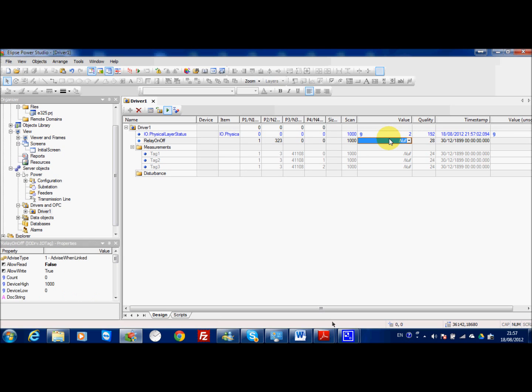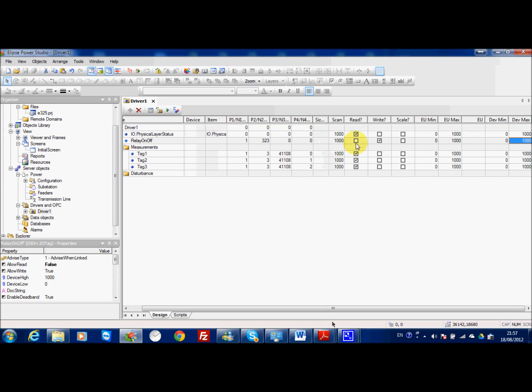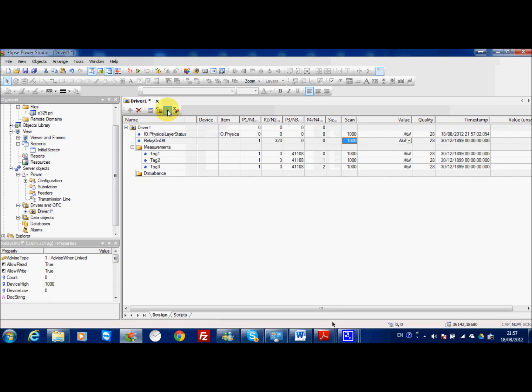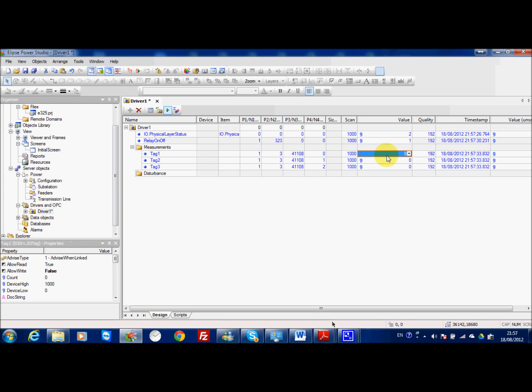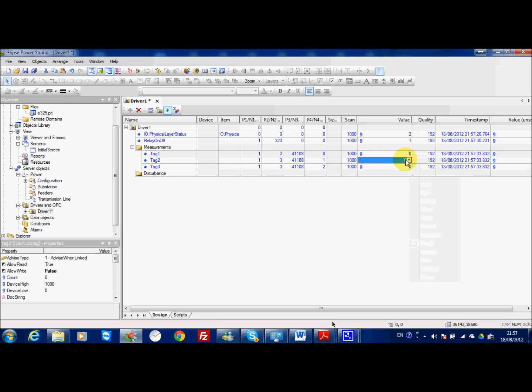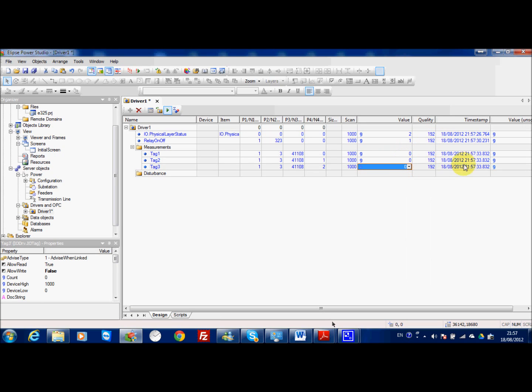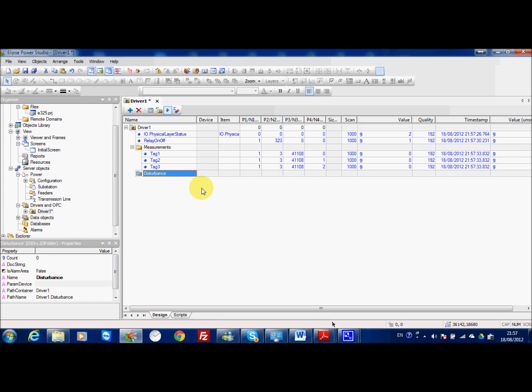Now here my relay on off needs to be set to 1. Of course if you want to you can also read and write to see the value. When you start the value is 0. Then I will write value to 1. When the driver starts you need some time and then you can get the value from this tag. So here the quality of signal means that the value is really reading from the device. Now I'm going to tell you how to use the disturbance record.